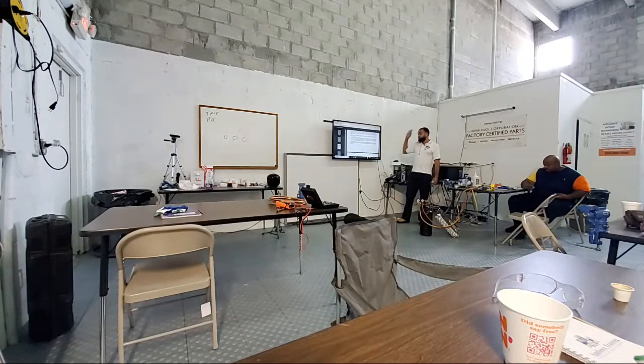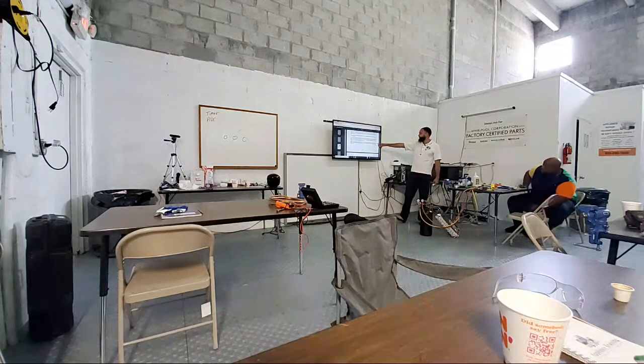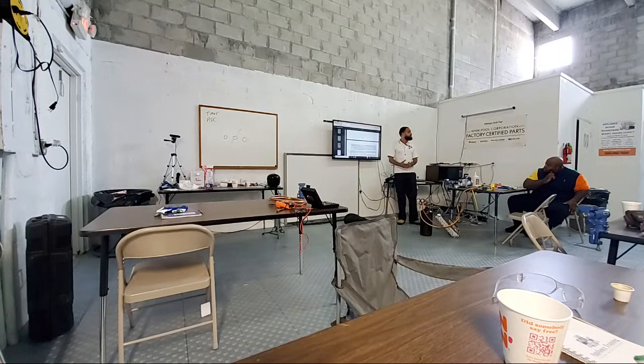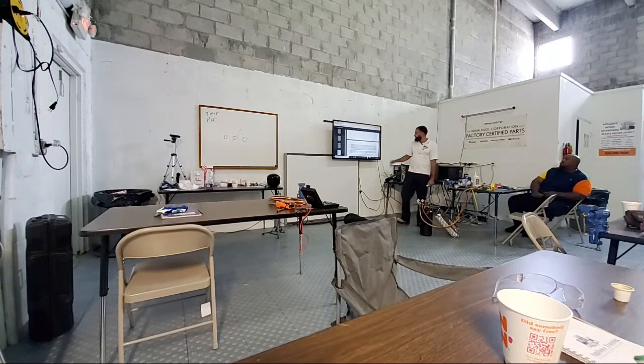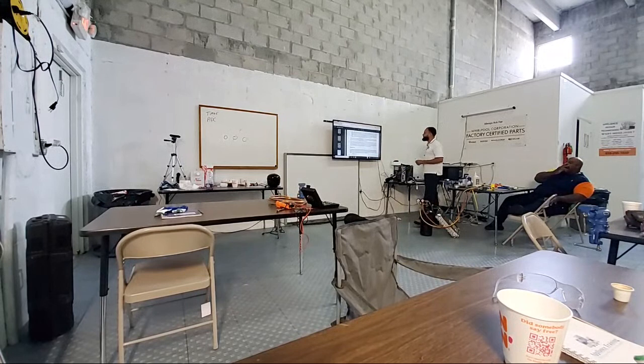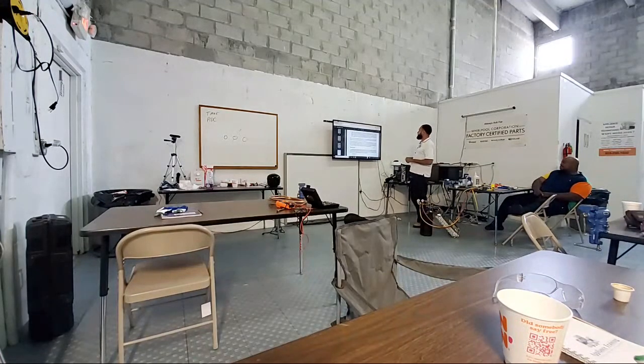All right? Again, if it takes longer than 12 minutes, the chip recognizes that the frost buildup was heavier and decreases the time between defrosts by 2 hours. So maybe the board says, okay, I've got to let it run less, defrost more. Again, it's trying to achieve that happy medium where it's not too frosted up and not too dry. The computer continues to monitor all of the described conditions and adjust the time accordingly until either the upper or lower limits of the algorithms are met.